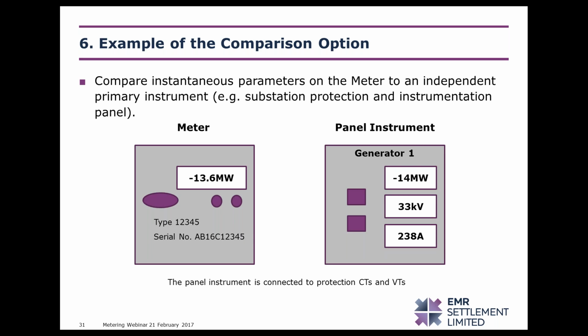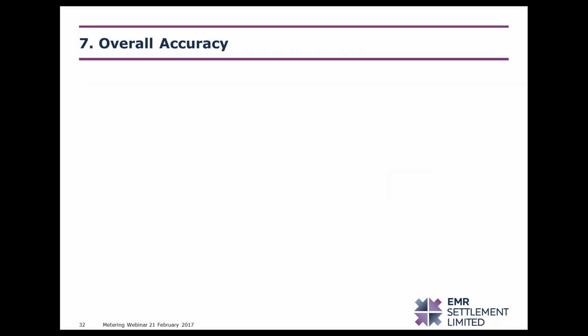These values are comparable and would be acceptable as proving that the measurement transformers have been commissioned for the CMU metering. This is not an accuracy test, and it is looking for ratio mismatches, reverse polarity, and incorrect connections. So as long as the values are approximately the same, it would be acceptable.